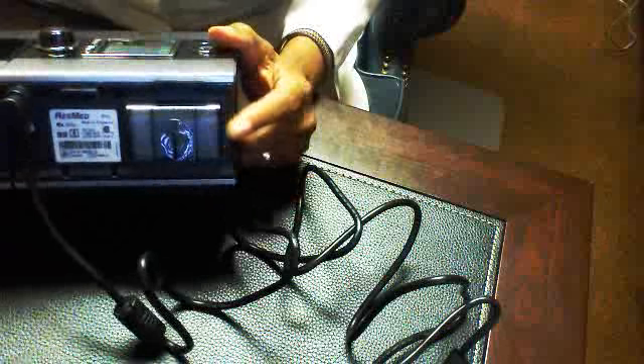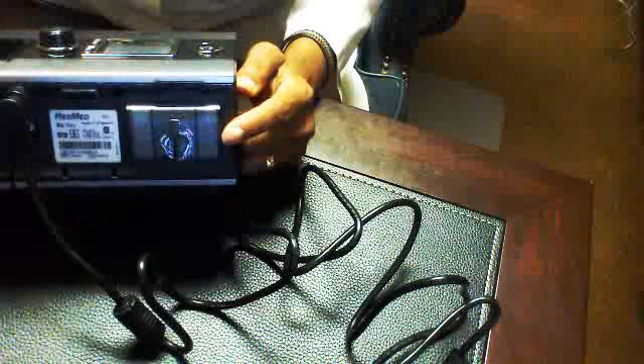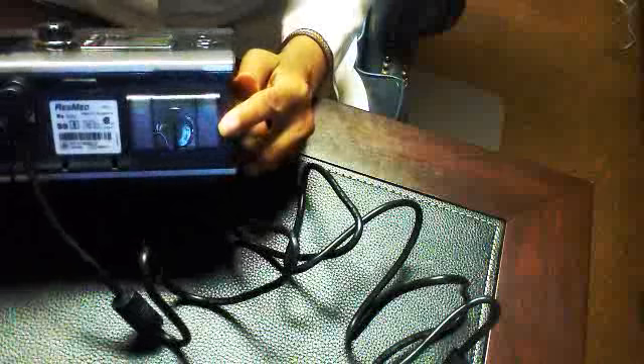The other thing in the back of the machine is the filter. The filter is a disposable filter which should be replaced about every 2 to 6 months. You will know that this needs to be replaced because it changes colors. If you live in a polluted area, you may need to change it more often. But I think you could get by with changing this about every 2 months.